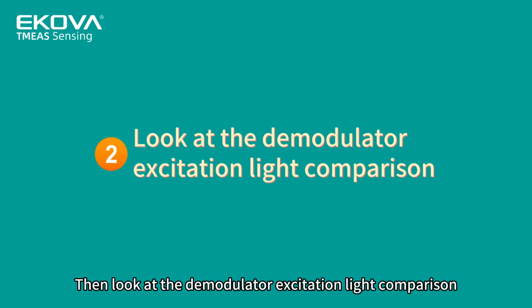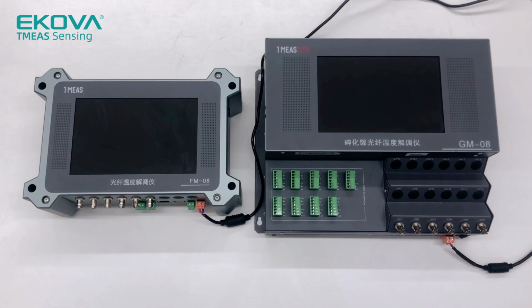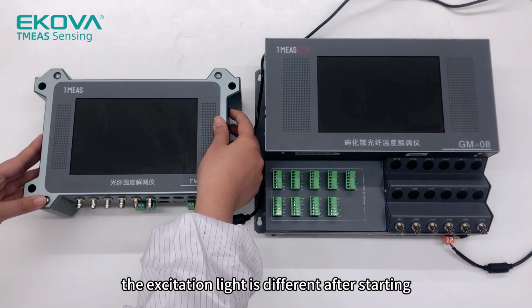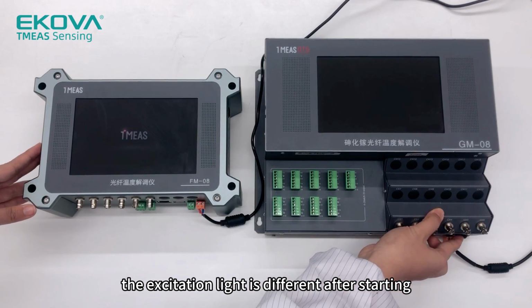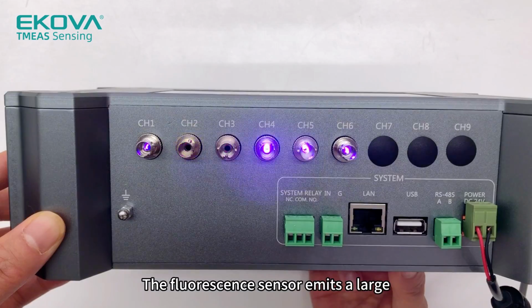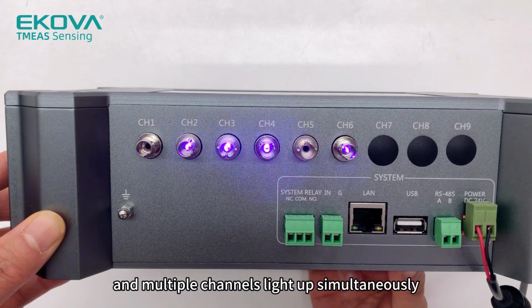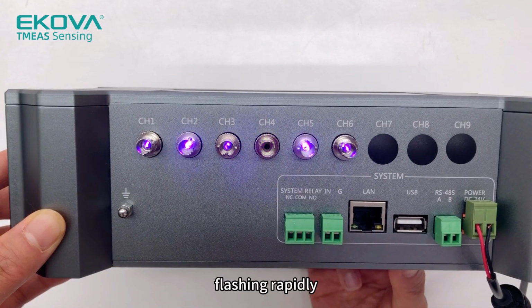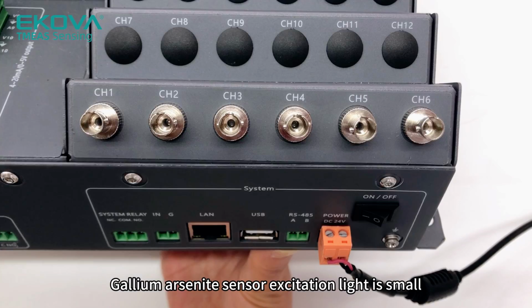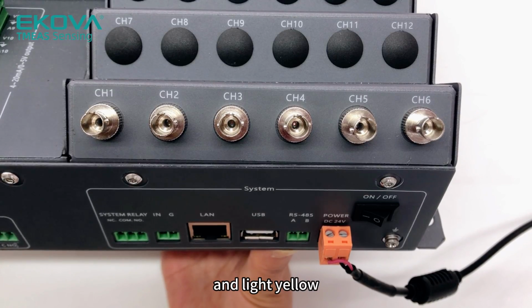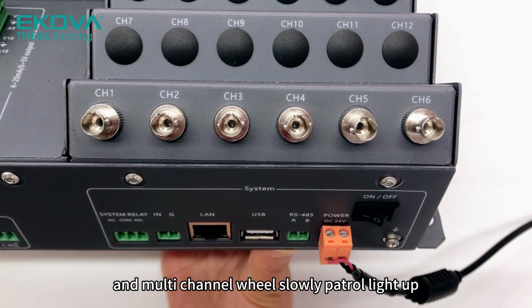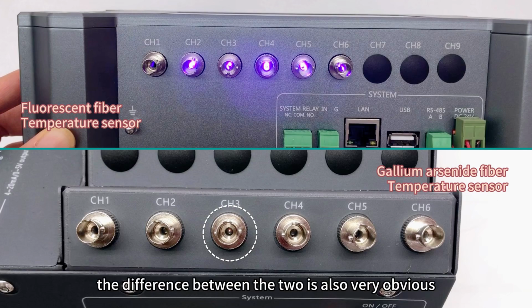Then look at the demodulator excitation light comparison. Different sensors have different demodulators, and the excitation light is different after starting. You can see the fluorescent sensor emits a large and bright purple light, and multiple channels light up simultaneously, flashing rapidly. The gallium arsenide sensor excitation light is small and light yellow, and multiple channels slowly patrol and light up in turn. Again, look carefully. The difference between the two is also very obvious.